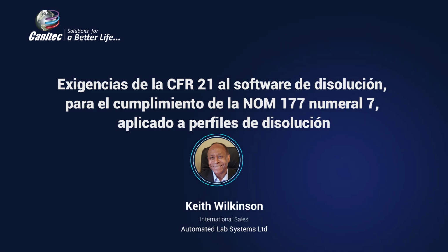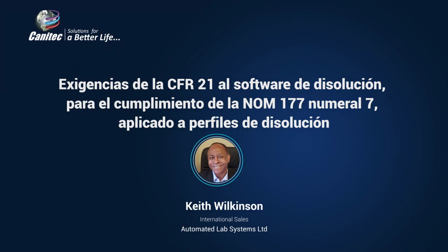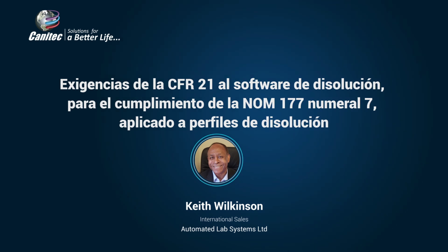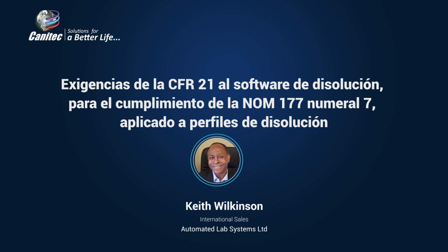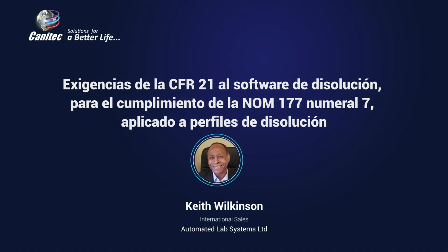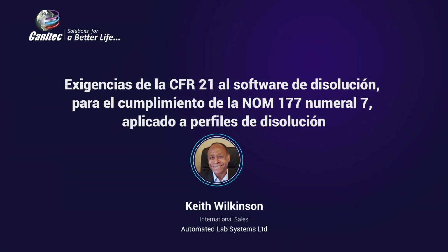In here, we have the USP acceptance. And this USP acceptance, the stages can be configured in IDIS and evaluated. These are the S levels. So yes, you can build up your specification, and then you can ask the software to test the sample against that specification, and it will tell you whether it's passed or failed and how it's failed.